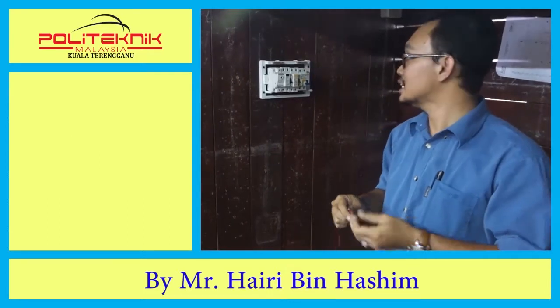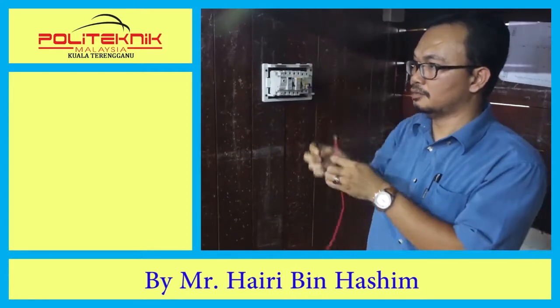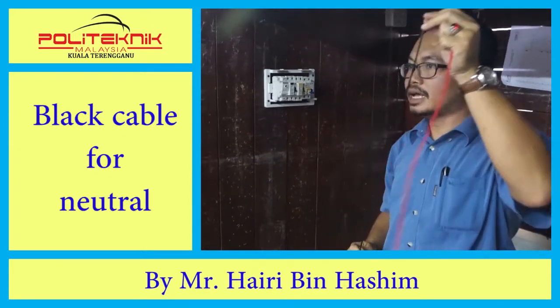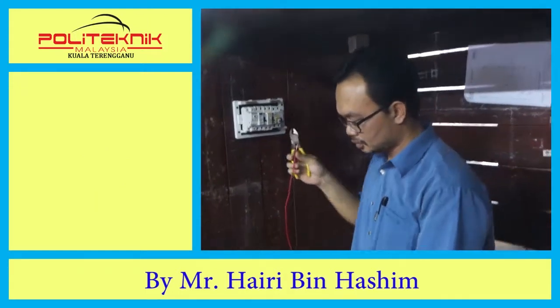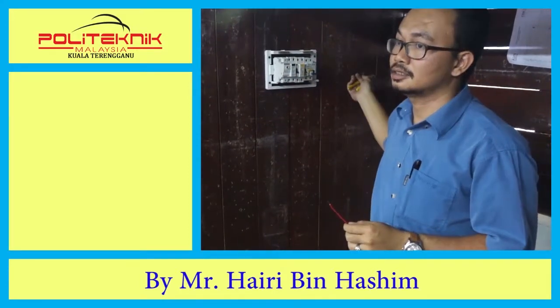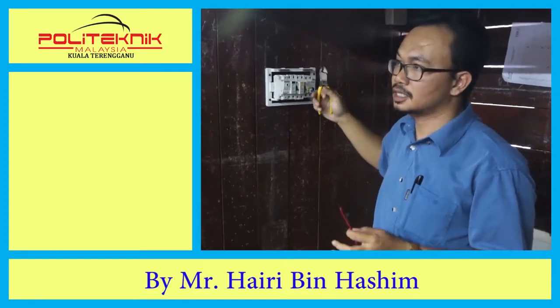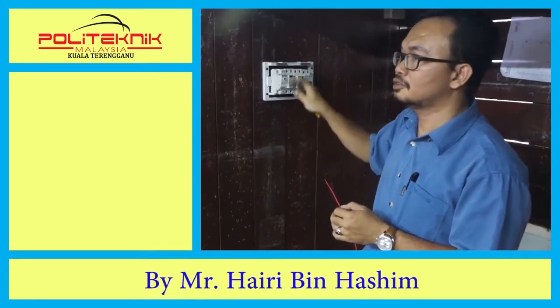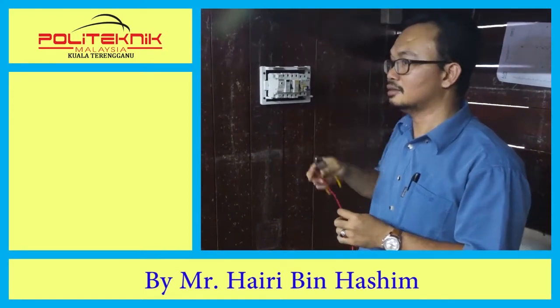For this I use black cable 1.5, because here we have 1.5 only. This is red for live, black for neutral, and green for earthing. I pick live. Make sure if you make a live connection, you go live to the end, and then you continue with neutral, because some people do both live and neutral together. But I prefer to do single line by line.